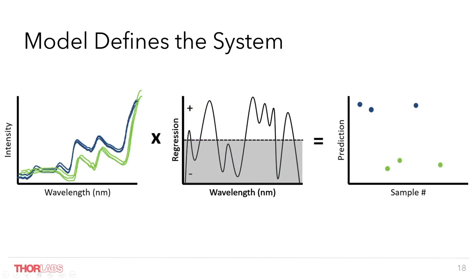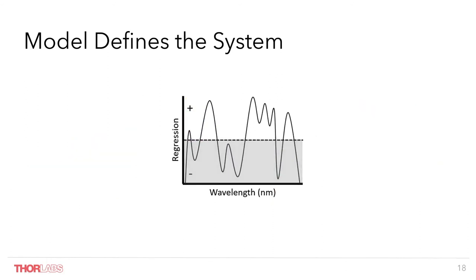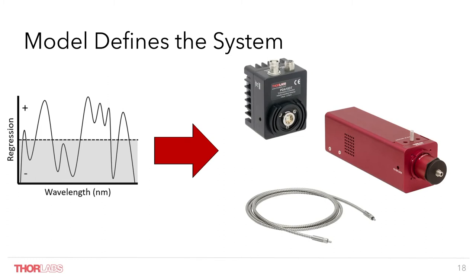While we are using the model for filter design, the model also allows us to determine the appropriate optical components in the system to yield the desired measurement characteristics. For instance, what light source is most appropriate, or selecting detectors to give us the greatest sensitivity with the MOE. This phase is also where we determine final packaging for the complete MOE system. Some of our customers already have a predetermined optical system, which could include optical path configurations, particular detectors, etc. So if you already have a system and would like to look at the potential of adding an MOE into that design, we can also work with you on that.